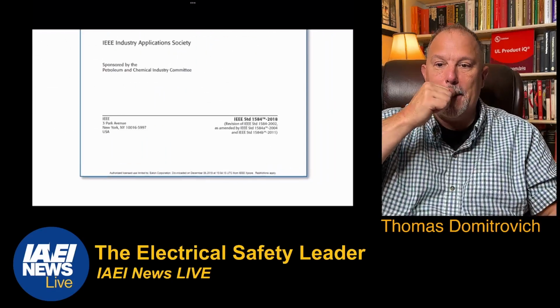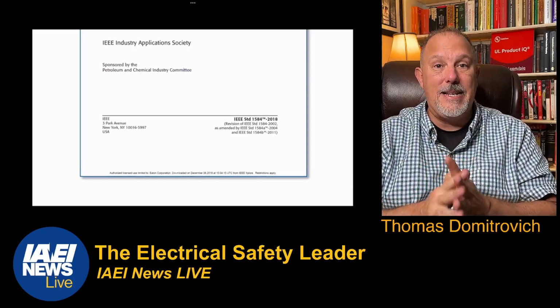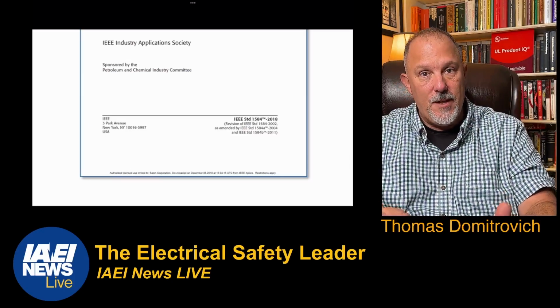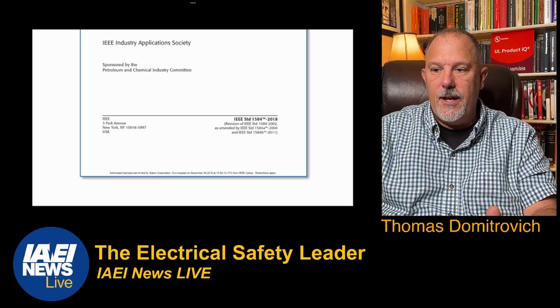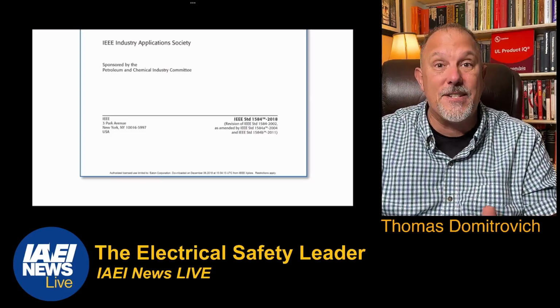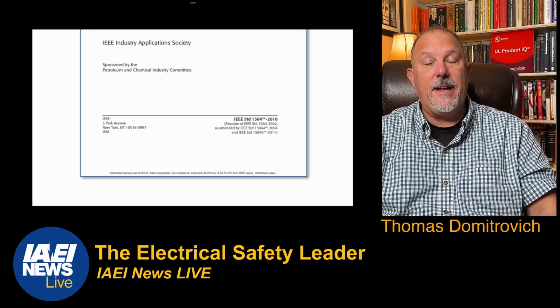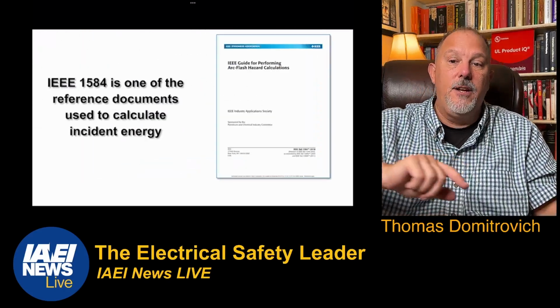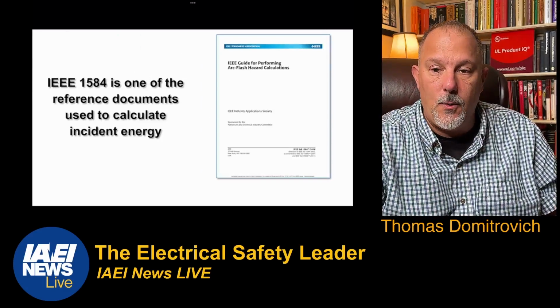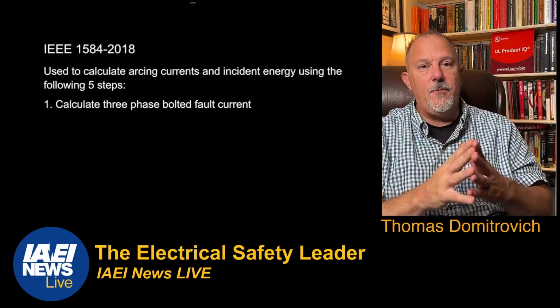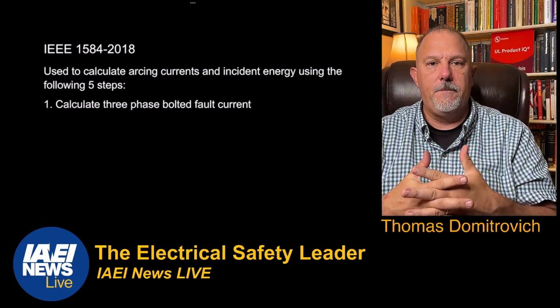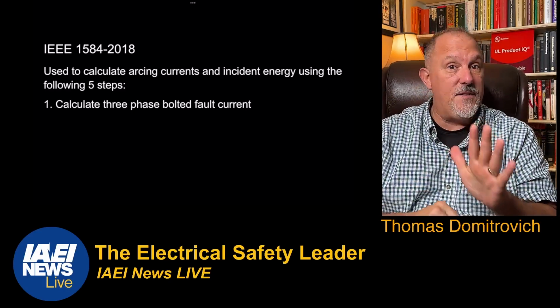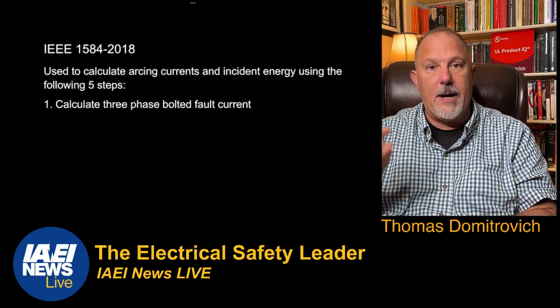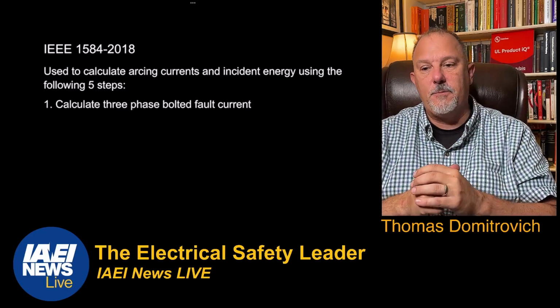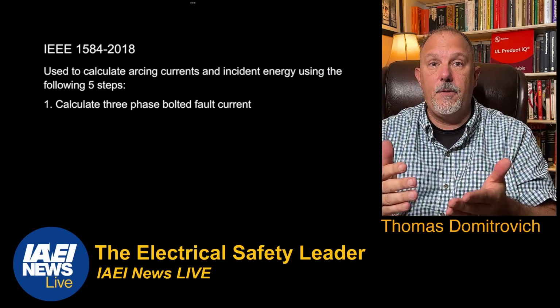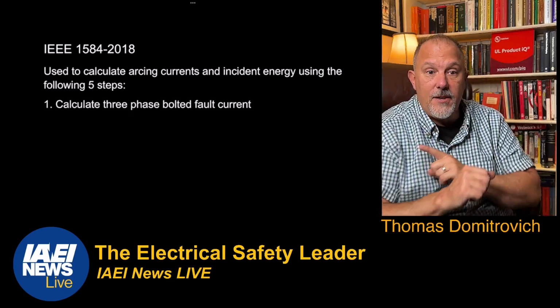The latest edition of this document is 1584-2018. So it was introduced in 2002. We did a lot of testing and research, and an update is provided 16 years later. And there's a lot of information that is now available in this document, but I'm going to help you understand the significance of IEEE 1584. So if I'm going to do an arc flash analysis, if I want to determine how much energy is at any point in the system, I need to do these 5 steps at each piece of equipment within the power distribution system. First, I need to calculate the 3-phase bolted fault current. We have many industry resources for doing this. I'll tell you the ones that I've used.